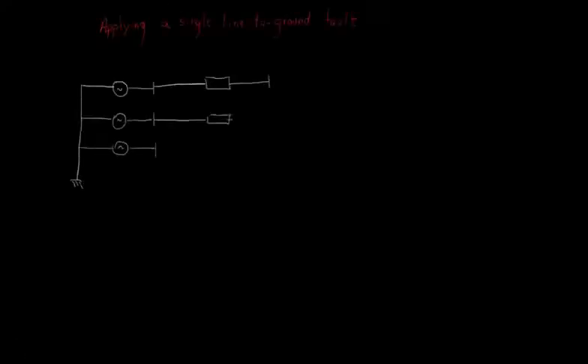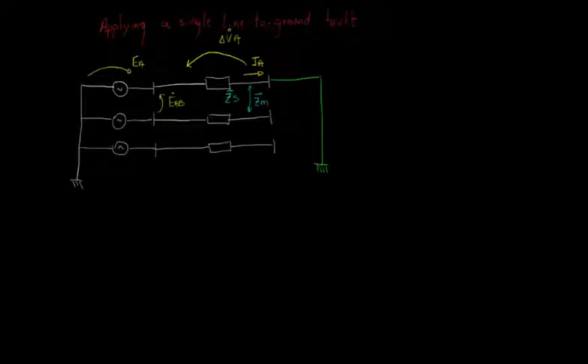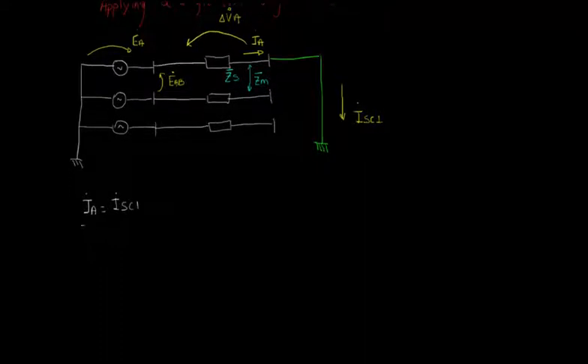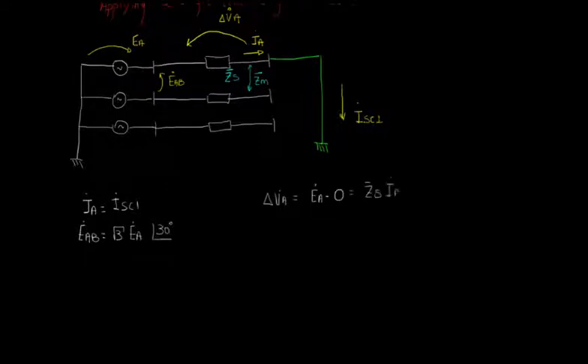We still need to find an expression for ISC1 and SSC1, so let's apply a single line-to-ground fault at the end of the Thevenin equivalent. In the same manner we did before, let's label the current on phase A as a single-phase short-circuit current. We still have this expression for EAB, and now notice that the current in phases B and C are equal to 0. Applying KVL in phase A, we have ZS times IA plus ZM times 0 plus ZM times 0, because phases B and C are open. Then, EA is equal to ZS times IA.